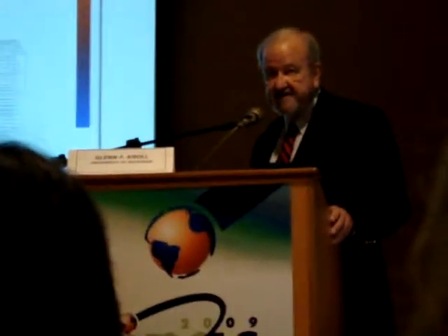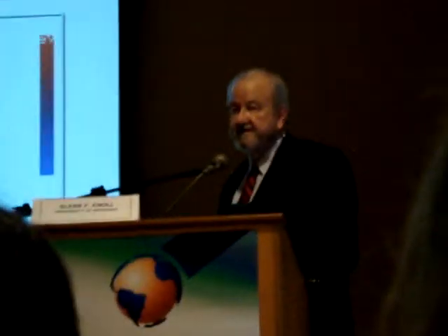Well, in a standard germanium detector or sodium iodide detector, that's done automatically because simply the charges add up because there's a single output node, or the light adds up in the scintillator. Even though it may be made up of 2 or 3 individual light flashes, they add together to give the output signal. Well, here you're getting separate output signals for each one of the interactions, so they need to be recombined electronically.